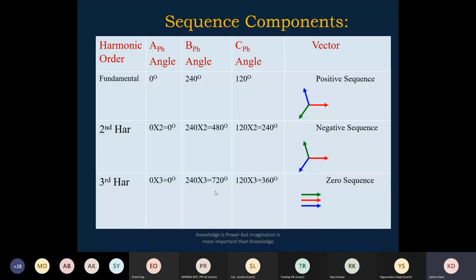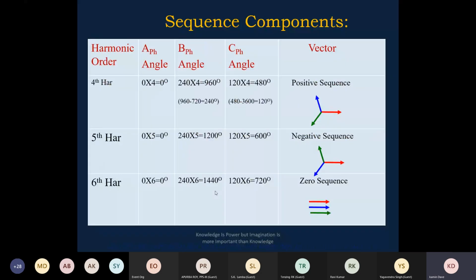So the imaginary component will be out, only the resistive components will be considered for the measurement, and that is the right measurement. Okay, so that is how the third harmonic is 0 degree, 720 degree, 360 degree. So that is called zero sequence. So positive sequence is the fundamental, second harmonic negative sequence, third harmonic zero sequence, then fourth harmonic positive sequence, fifth harmonic negative sequence. And in transformer over excitation conditions, the core is getting saturated.